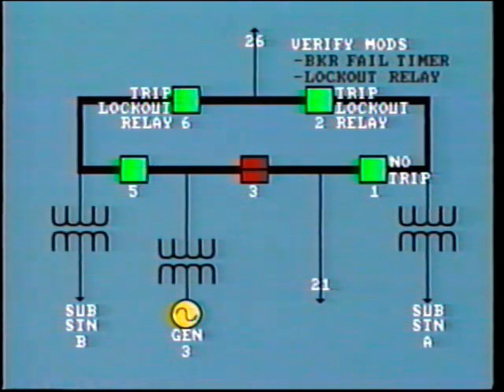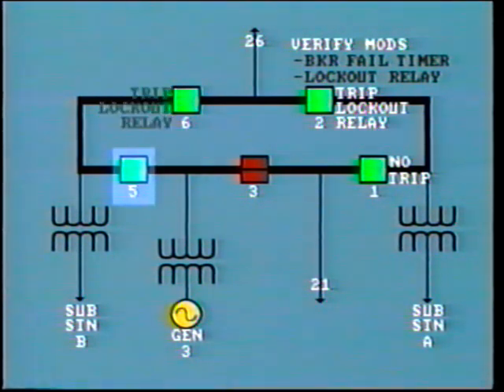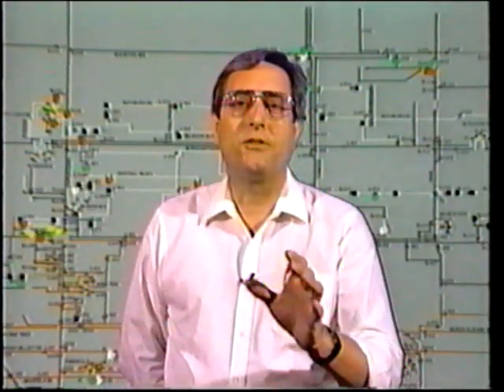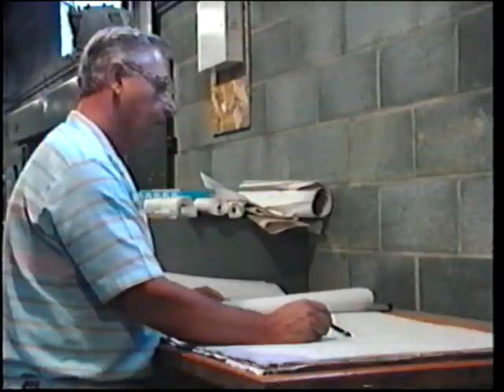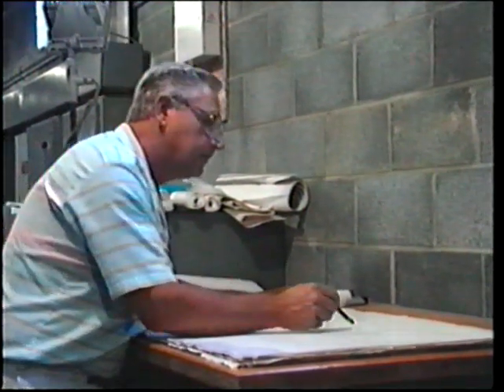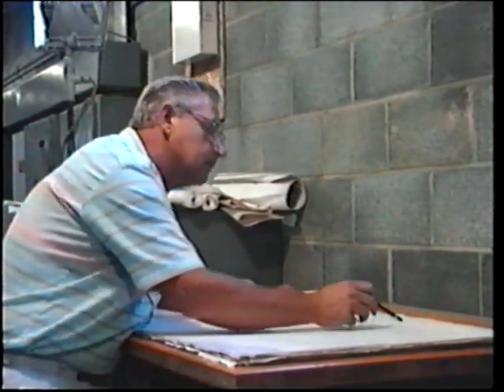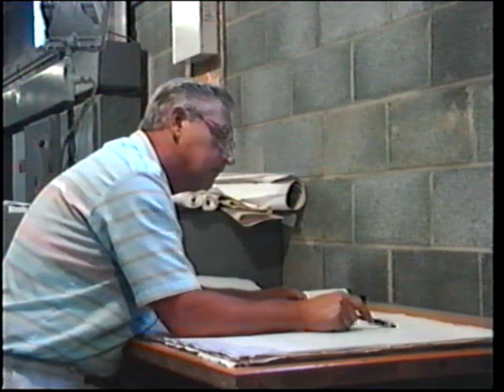Now the technicians knew or should have known that breaker 5 was in service and that tripping the lockout relay may indeed trip that breaker. They should have stopped the actual testing and investigated further until they could have positively identified the lockouts and verified that the wiring really was disconnected or not. Now, in this example, there are several lessons for all of us to learn. First, be prepared. This means a thorough review of the task before you start. Know what could result from your actions.